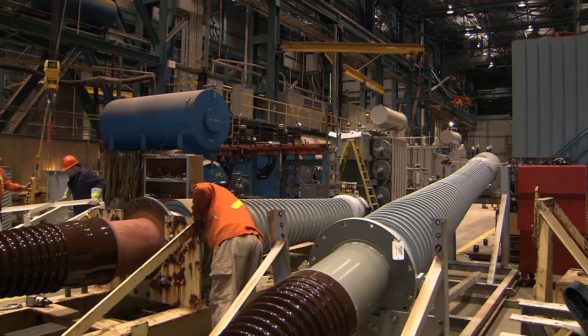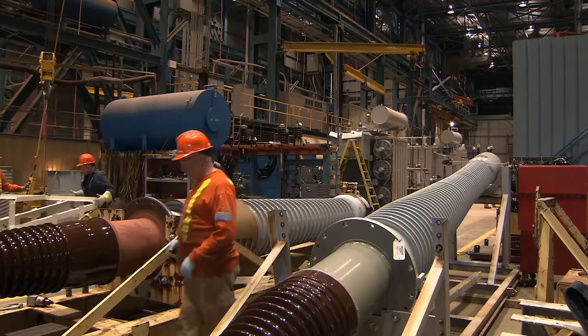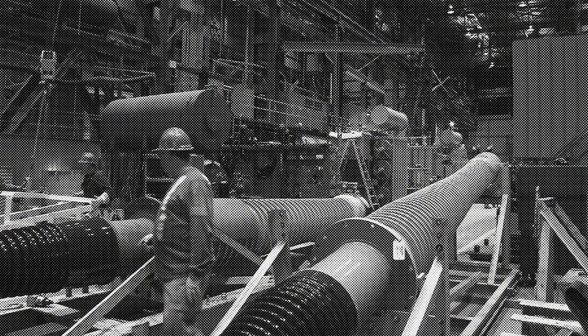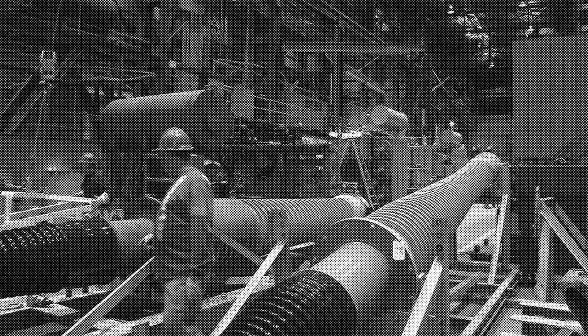Large bushings, such as the ones here, are regularly moved in and out of the area on transport carriers, which are basically metal frame structures with supporting rests along the length of the bushing. The mounting flange of the bushing is itself bolted to the metal frame of the transport carrier to prevent it from being damaged in transit.